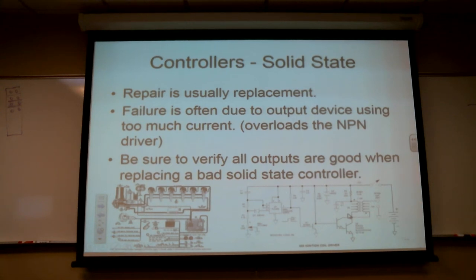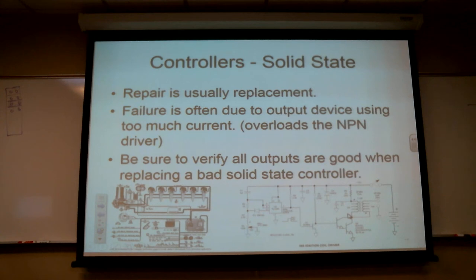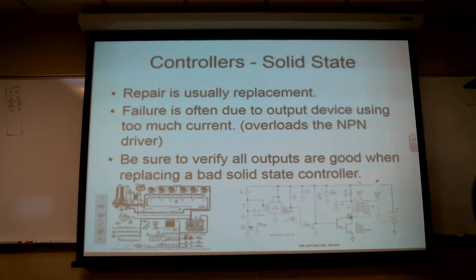There's nothing wrong with documenting the problem — if it's got cracked solder joints, take a picture, show the customer, explain why it took nine hours to figure out. I cannot say this enough: any time a solid-state controller has gone belly up, make sure the outputs aren't overloading it.